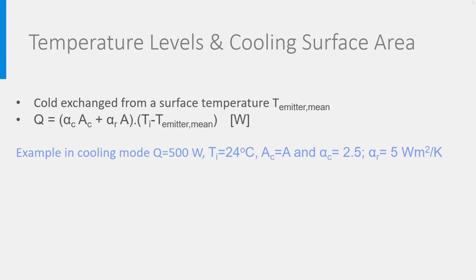Let's look further into these surface areas in hydronic cooling and take an example where we need 500 watt cooling to keep the room at 24 degrees Celsius. The formulas are identical to the formulas for hydronic heating. We assume a radiative heat transfer coefficient of 5 watt per square meter Kelvin and a convective one of 2.5.